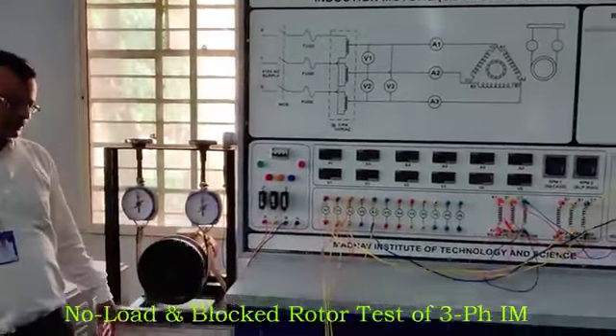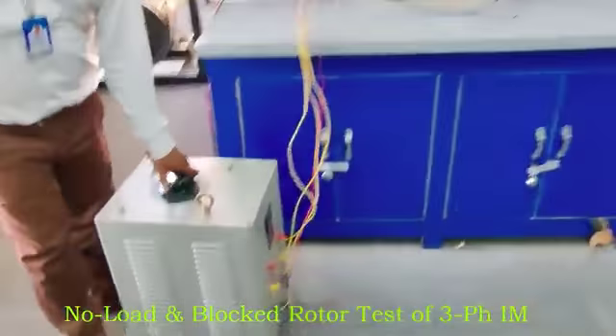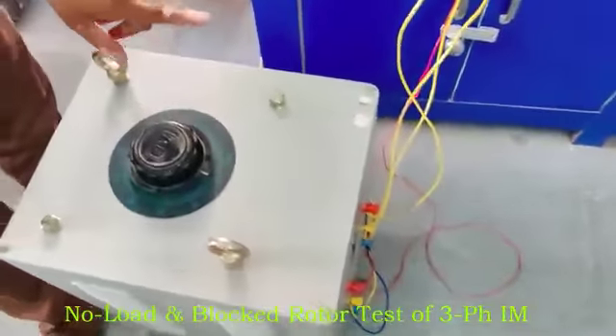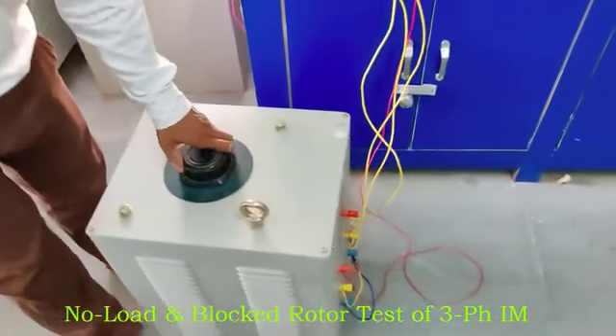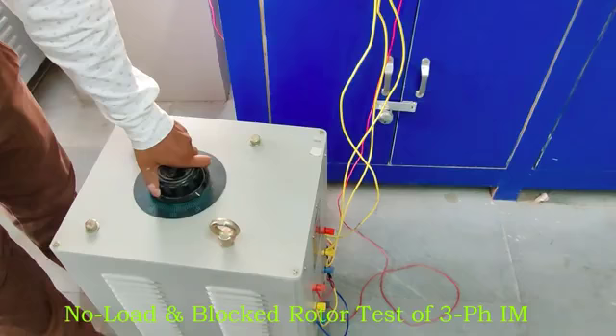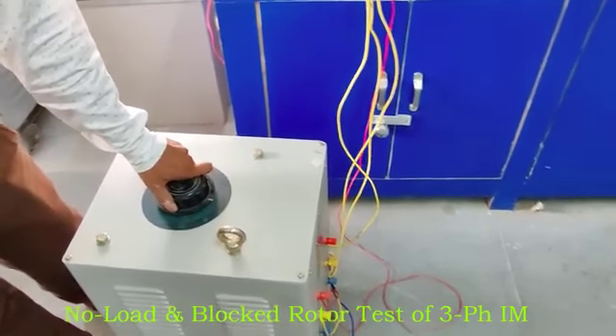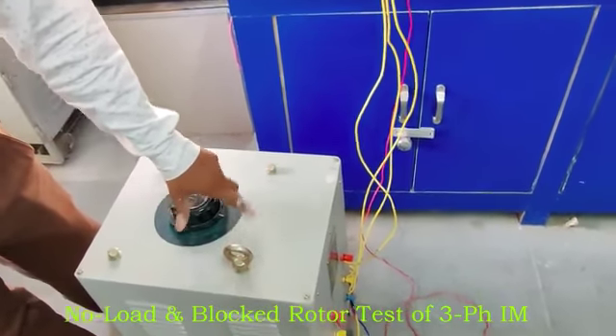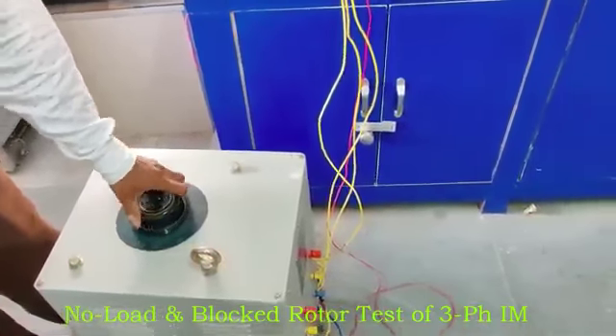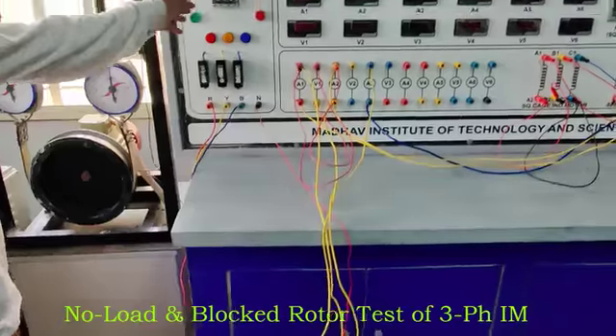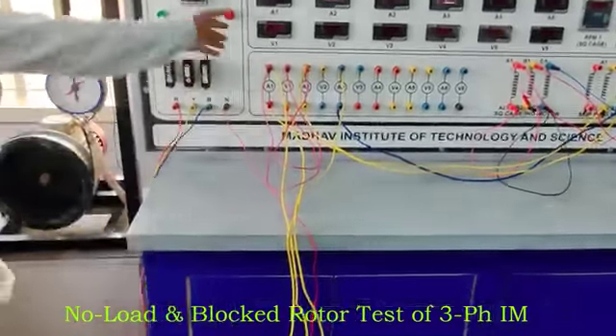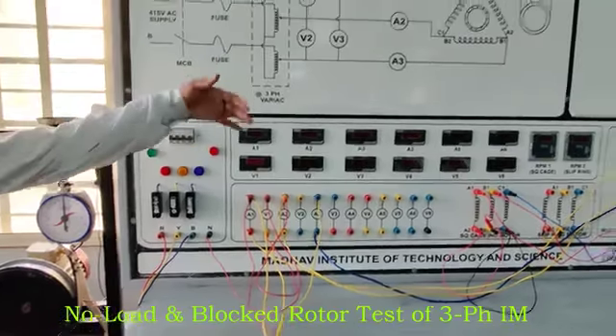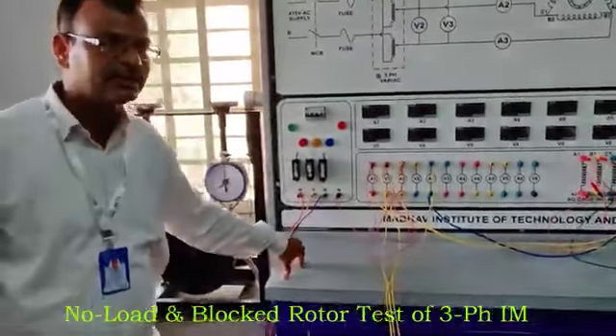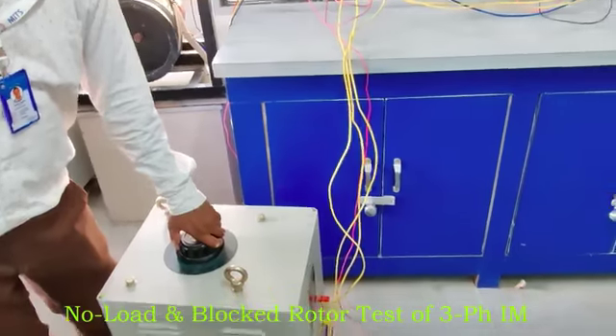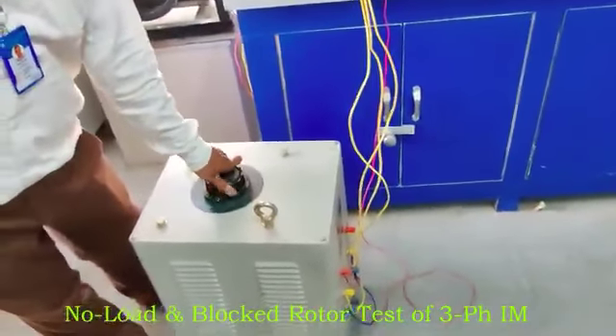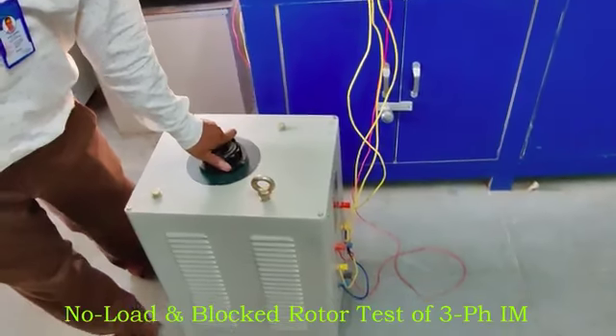So with the help of the auto transformer, you have to increase the voltage gradually. Second thing, the main precaution to remember while you perform any experiment: the auto transformer should be kept at zero position. Otherwise, suppose the connection is wrong and you just start, in that case high voltage will go into this machine and the meters and voltmeter may be damaged. So this is the main precaution when you perform any experiment in electrical engineering with an auto transformer. It is kept at zero position.